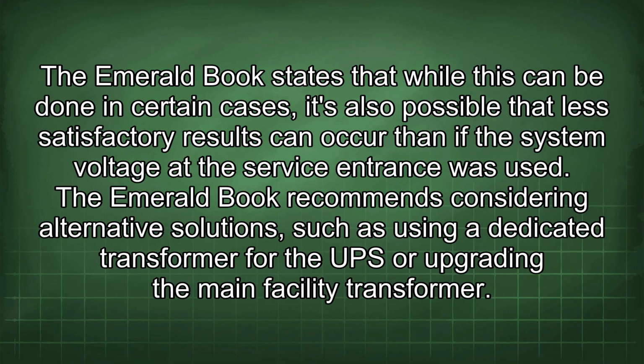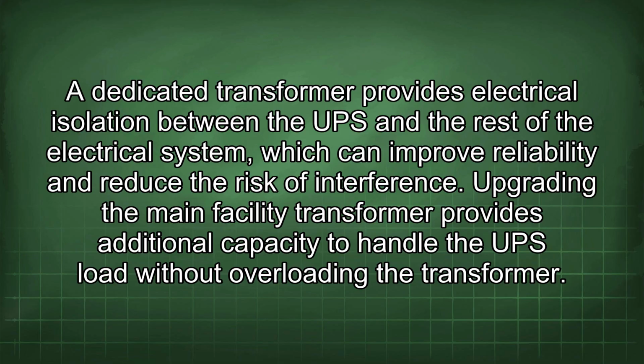The Emerald Book recommends considering alternative solutions, such as using a dedicated transformer for the UPS or upgrading the main facility transformer. A dedicated transformer provides electrical isolation between the UPS and the rest of the electrical system, which can improve reliability and reduce the risk of interference. Upgrading the main facility transformer provides additional capacity to handle the UPS load without overloading the transformer.